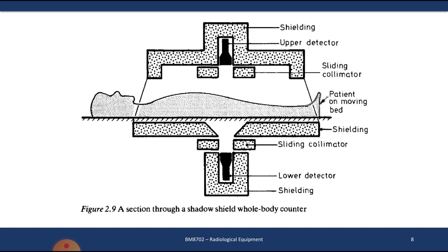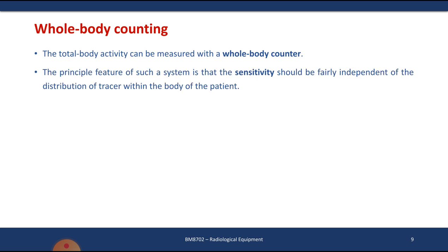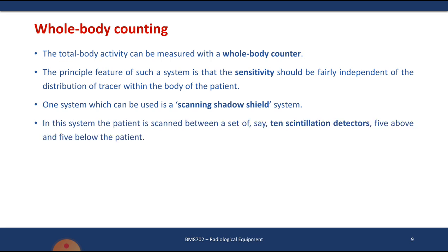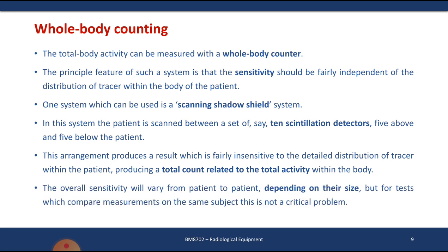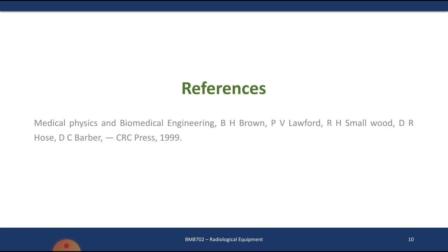The fourth application is the whole body counter, which measures the total activity of the body. Its principal feature is that sensitivity should be independent of the distribution of the tracer within the patient's body. It has a scanning shadow shield system with around 10 scintillation detectors — five above and five below — detecting radioactivity throughout the body. However, sensitivity can vary depending on the patient's body size, for example between an obese adult and a small child. These topics can be referred to further in the BH Brown textbook.